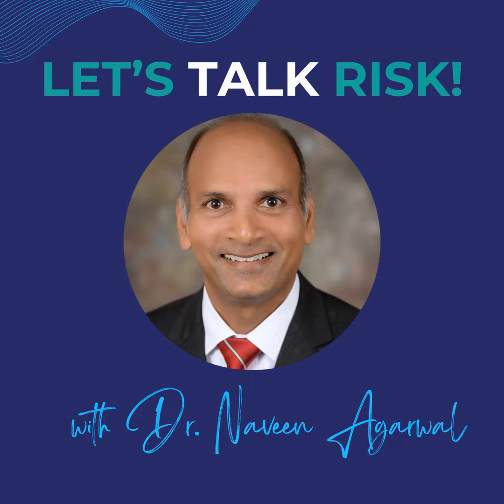Level 4 is partial, where the automation is doing a lot, but the human's watching. So when you think about physiological closed loop control systems, like an artificial pancreas, that would be a level 4. That human needs to be able to intervene if anything's going wrong. And then full automation is where the human's out of the loop. So we're not really there on anything in medical. But as we think about this, there's level 4 in particular I want to talk about.